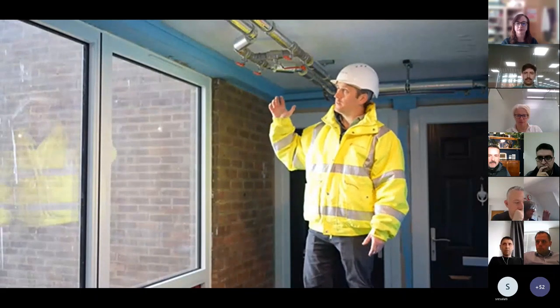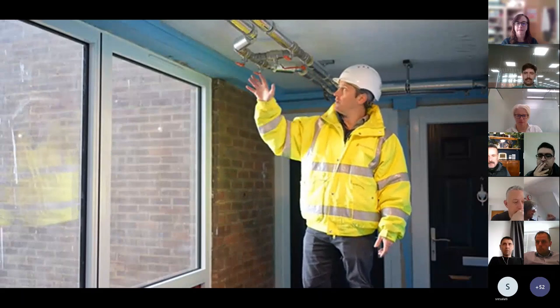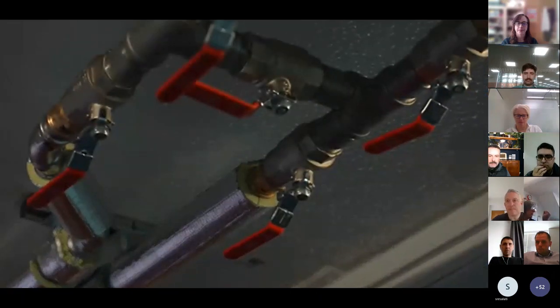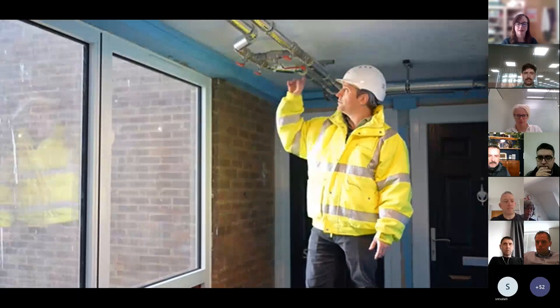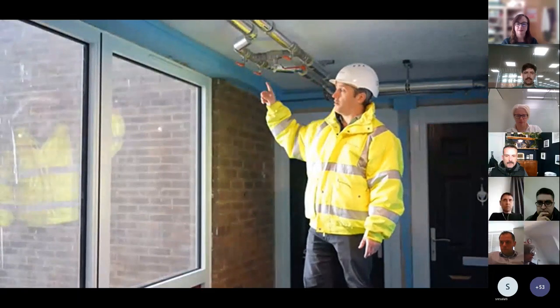At that point, once we're ready to undertake the installation, we can isolate the risers. The heat pumps will be installed and connections made into the flow and returns here. We can then open these three valves and flow and pressure test from the heat pump through this circuit.